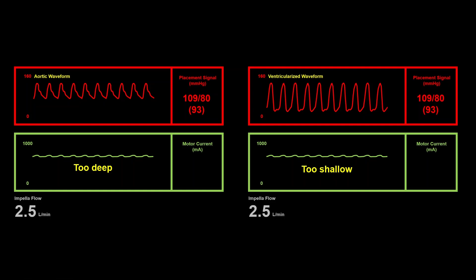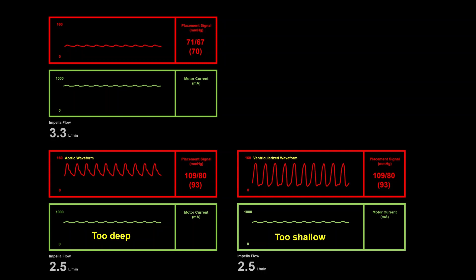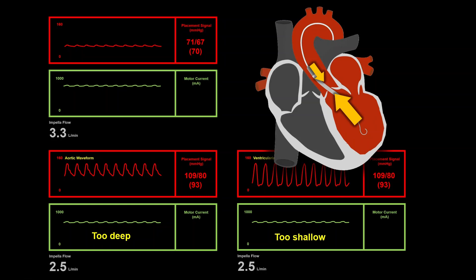Although a flat motor current waveform should at least make you consider if the Impella is improperly positioned, there is one important situation where a flat waveform can indicate appropriate pump position and function. And that's the waveform we see at the upper left, where the aortic placement signal and motor signal currents are relatively flat. This situation can indicate a well-functioning Impella and a very weak heart. If the heart is barely pumping, you may not see much pulsatility on the aortic waveform, and consequently, there may not be observable pulsatility on the motor current waveform. This is actually an optimal condition for Impella efficiency, which leverages the increased preload in the left ventricle and reduced afterload in the aorta to deliver blood more efficiently through the cannula.